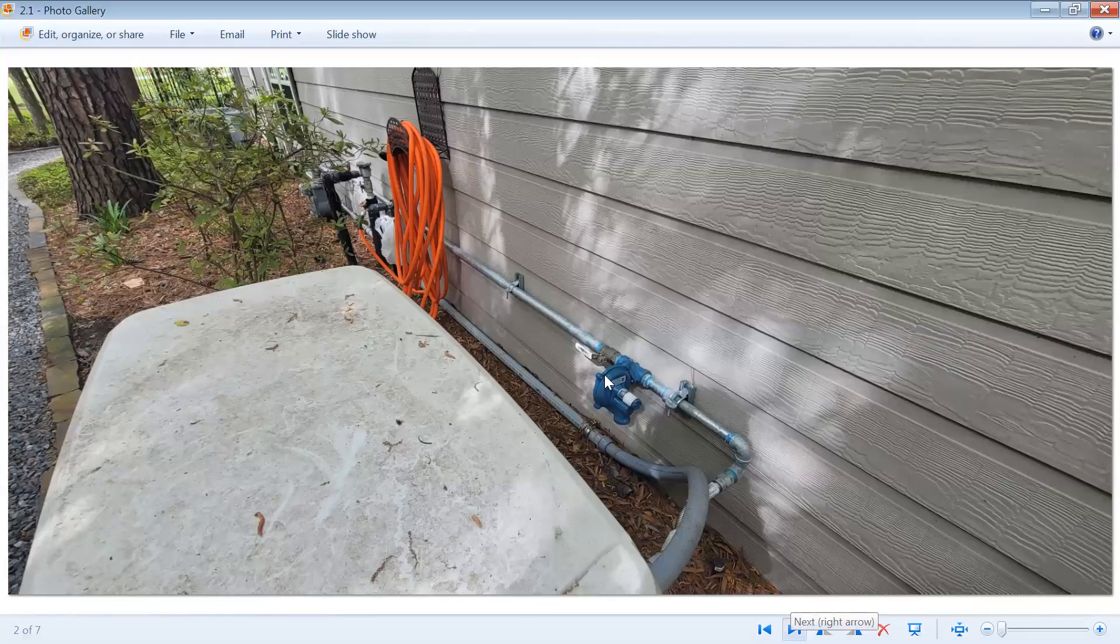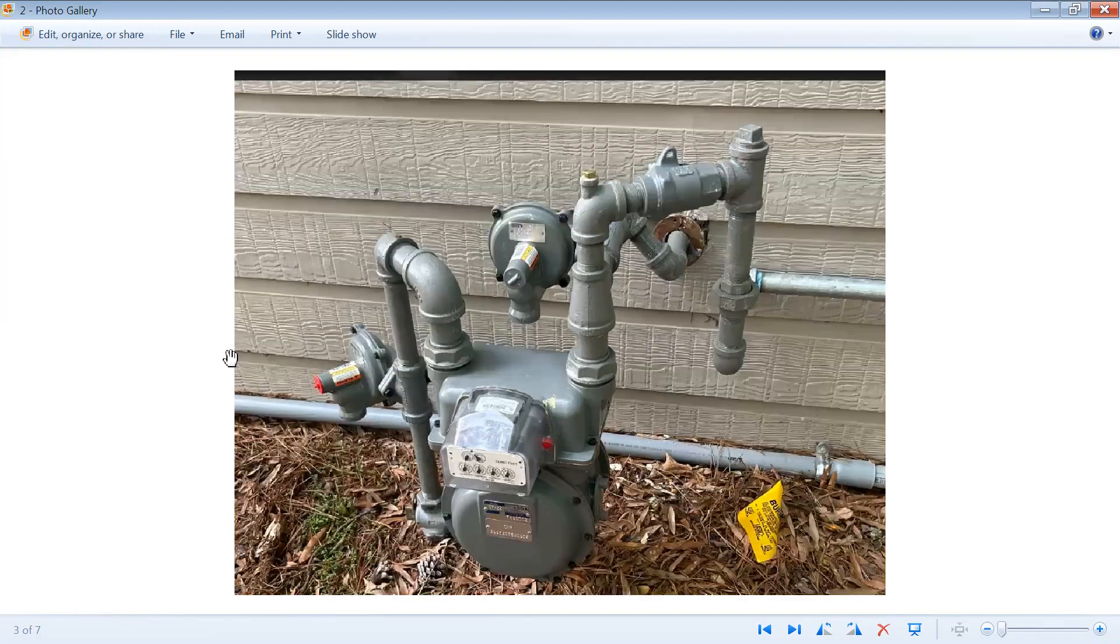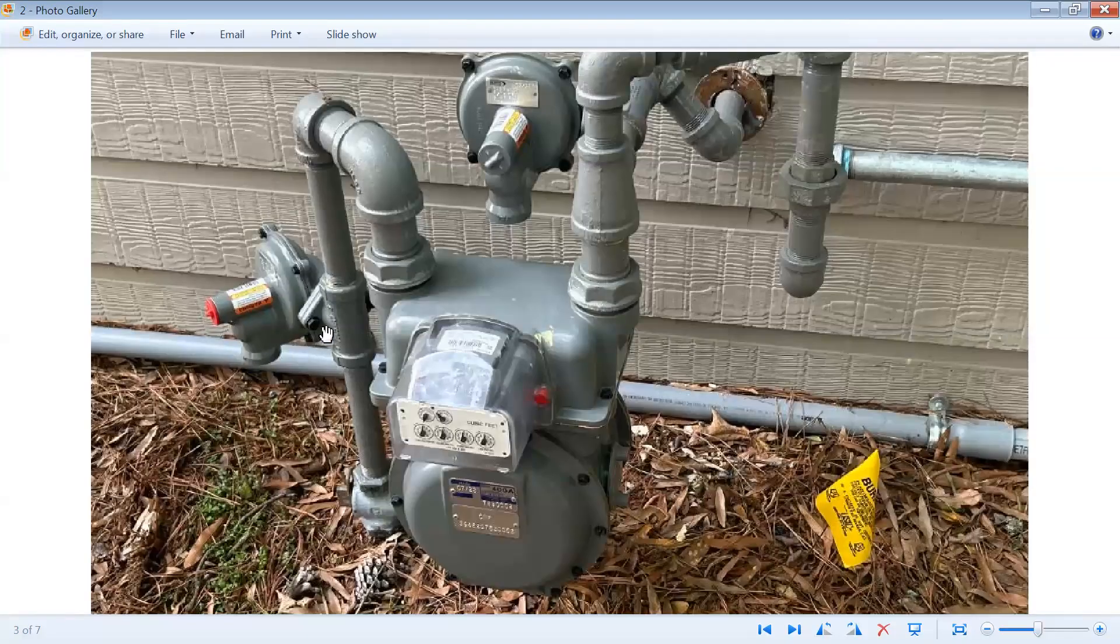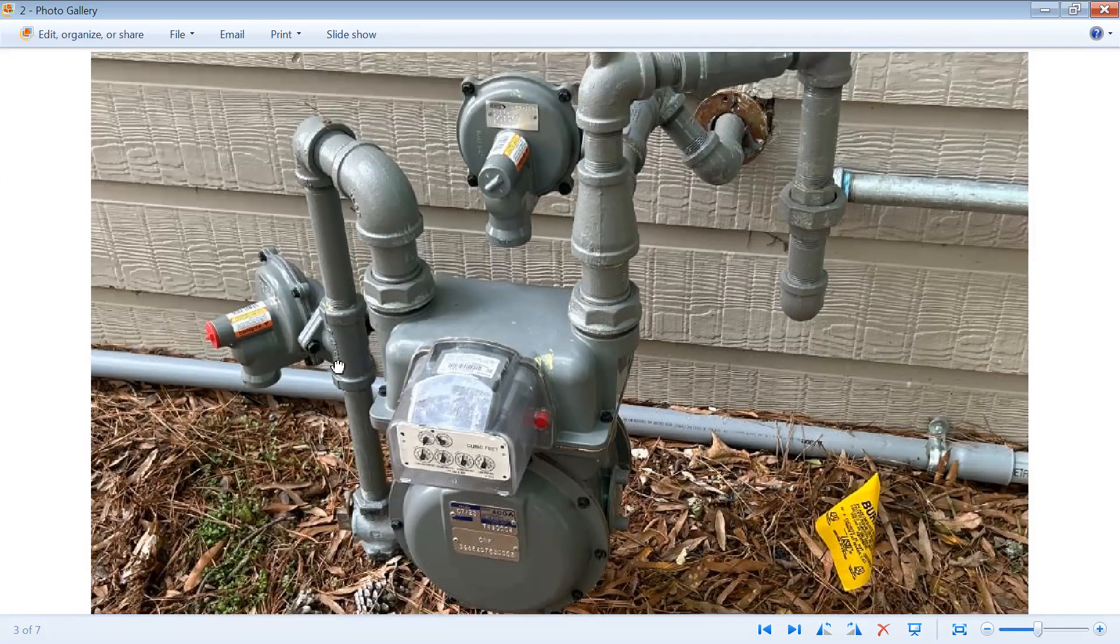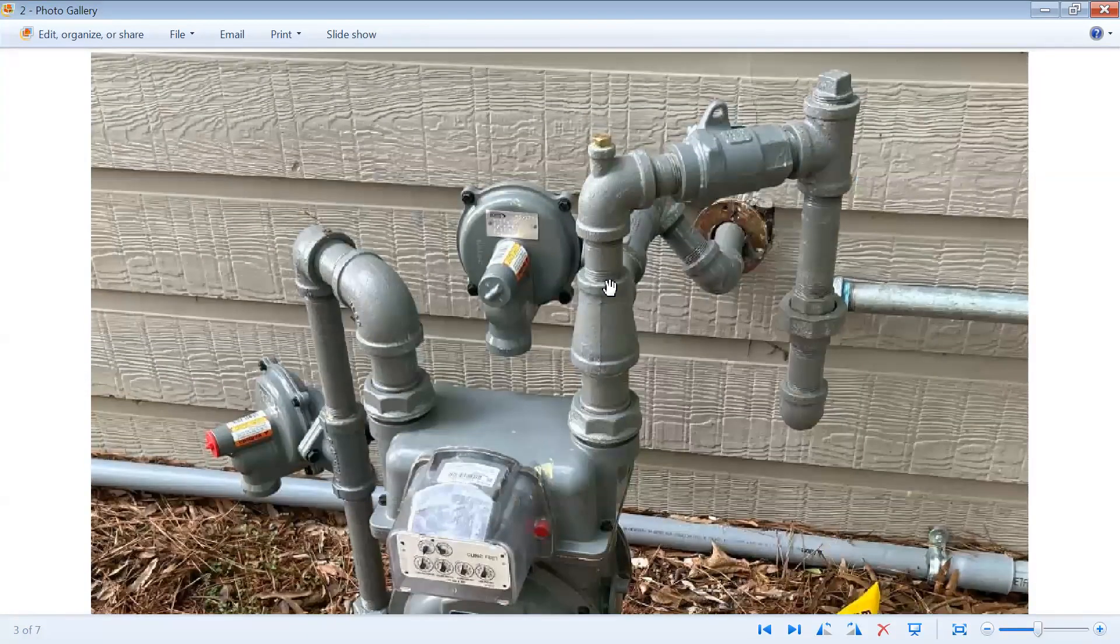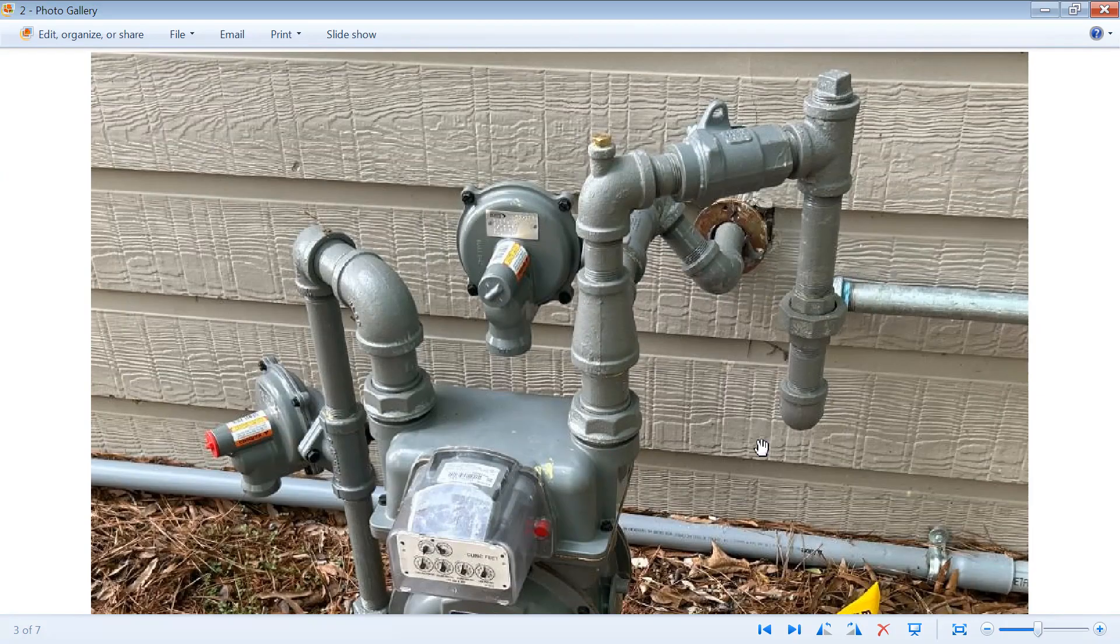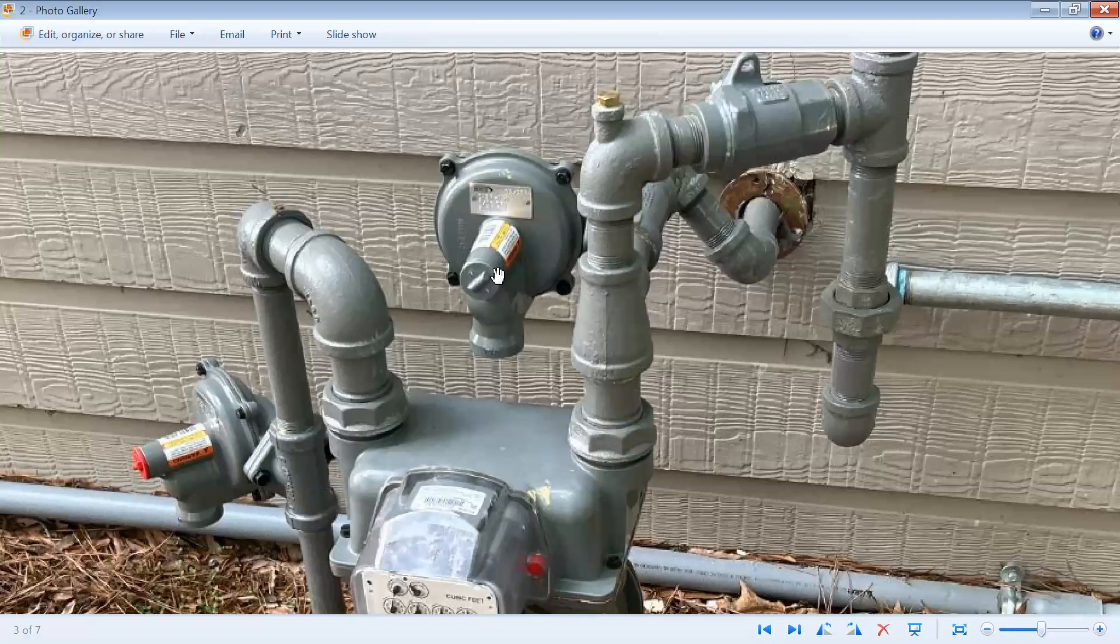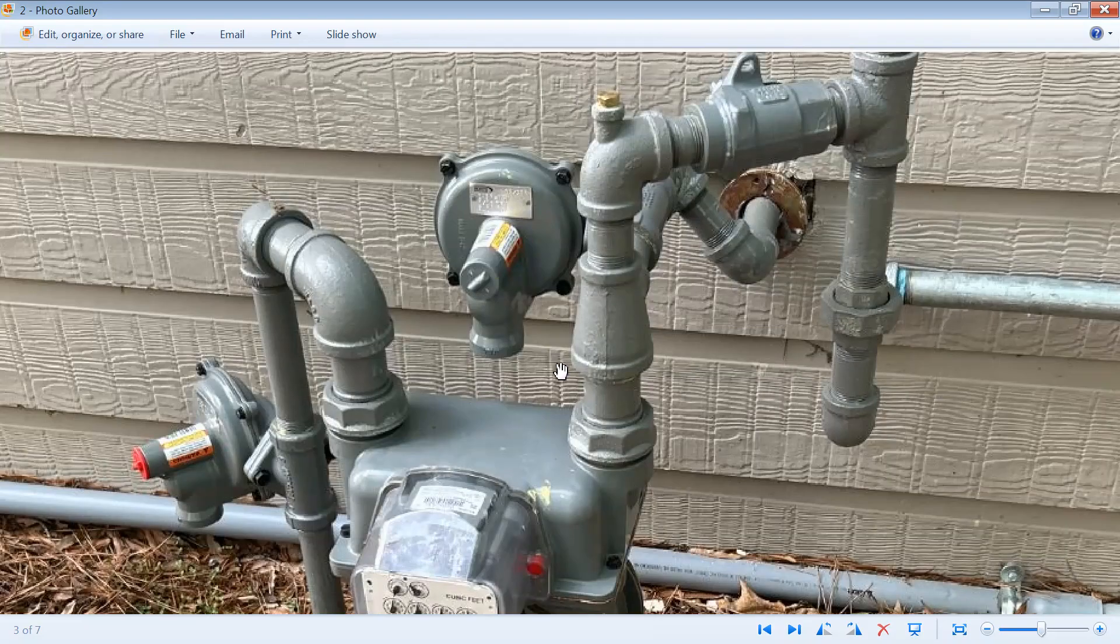This is what happened after I talked to the homeowner and explained that the gas requirements they need for the heater and generator need to come off what I explained earlier on the high pressure side, and that's exactly what this regulator is. It's very easy to identify because it has a red knob on the end. The gas line being high pressure comes up through the gas meter, continues to be a high pressure system, and then feeds off to the generator. We plumbed the gas heater on this side of the line. What goes into the house, you see here, is the half-pound low pressure side regulator for the inside of the house.